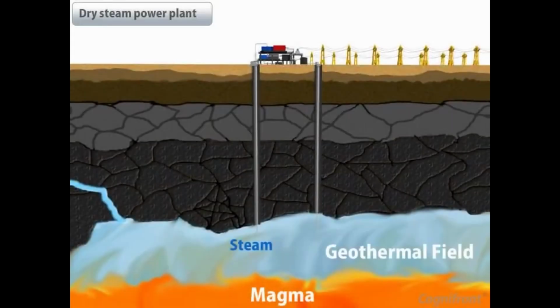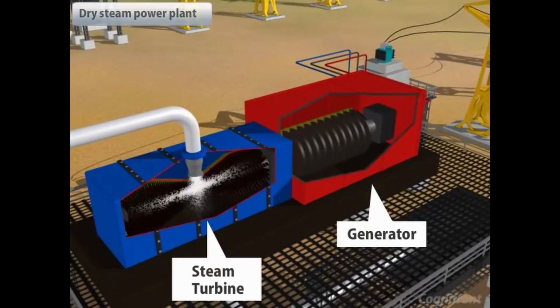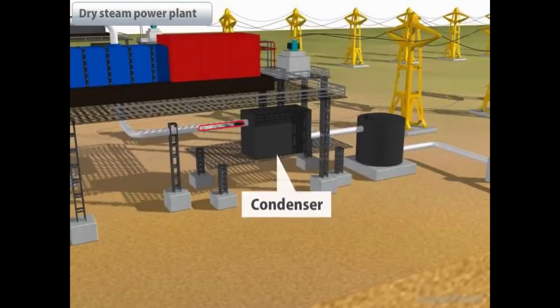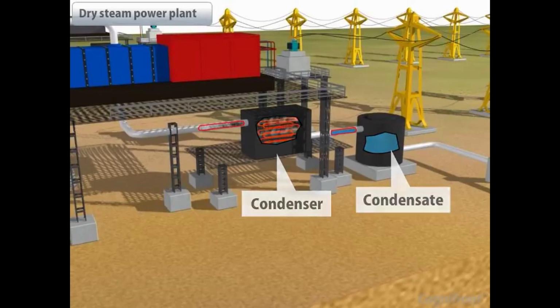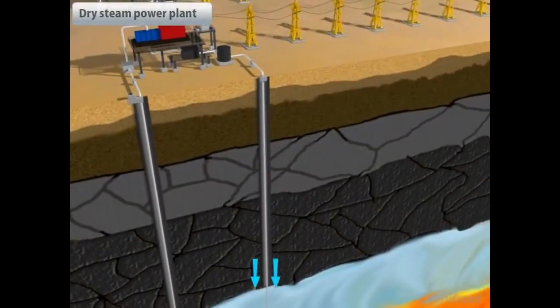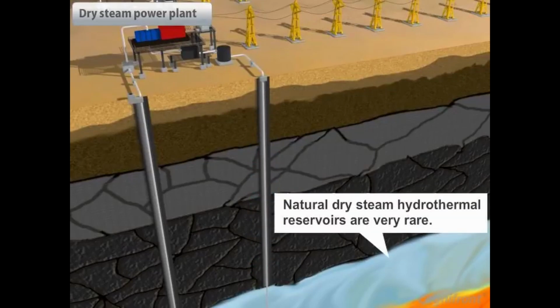The first type of geothermal power plant is called the dry steam power plant. If an area has geothermal heat which emits steam from the geothermal reservoir, then the steam can be directly used. The steam is extracted and directed towards the steam turbine, which is coupled with a generator. The flow of steam causes the turbine to rotate, causing the generator to produce electrical energy. After that, the steam is directed towards the condenser, where it is converted into water. The water is then pumped back into the earth to begin the process again. This type of geothermal power plant is not common because steam reservoirs are rare.